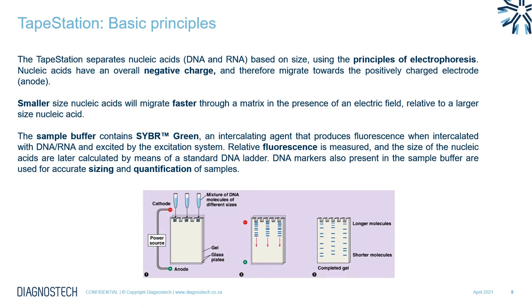The TapeStation separates nucleic acids based on their size using the principles of standard gel electrophoresis. Nucleic acids have an overall negative charge and therefore migrate towards the positively charged electrode, the anode. Smaller nucleic acids migrate through the gel matrix at a faster pace in the electric field compared to larger fragments, allowing separation based on size. The sample buffer contains the SYBR Green intercalating dye, which binds to DNA and RNA and is then excited by lasers in the system, allowing measurement of relative fluorescence. This gives an indication of the size and concentration of your sample, measured against a ladder and DNA markers of known size and concentration, which are used to normalize and align samples in the run.